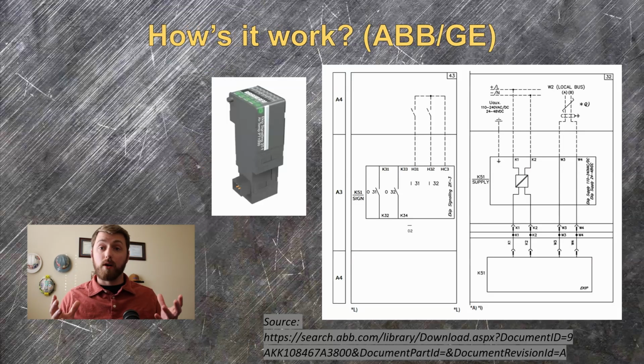Okay, so how does it actually work? Again, I'll have to generalize because it can be implemented in a million different ways, tailored to each installation for each type of breaker, for each switchboard. But for most installations I've seen, they work the same and they're all fairly simple. There's going to be a power supply in the switchgear, usually supplying 24 volts DC whenever the bus is energized. When the blue switch is turned on or placed into maintenance mode, it sends a 24 volt digital input into the breaker's trip unit. The trip unit then enables the new setting and closes a status contact, sending 24 volts back to the indicator light, telling you, the operator, that the system is actually in maintenance mode.